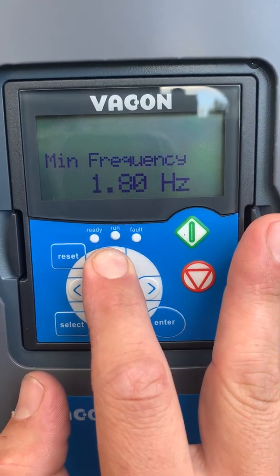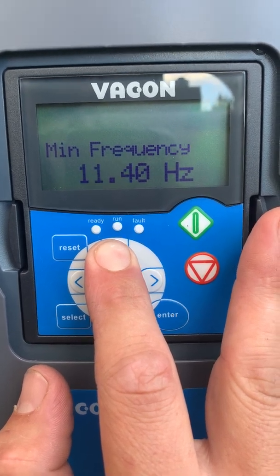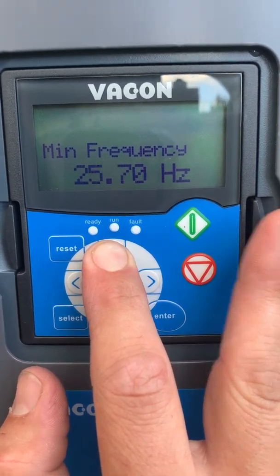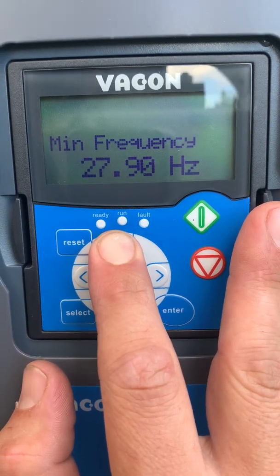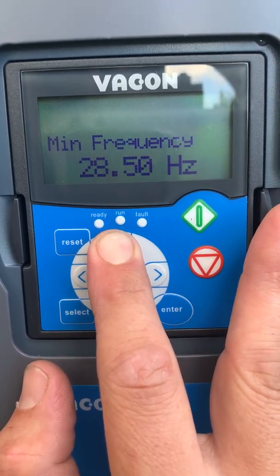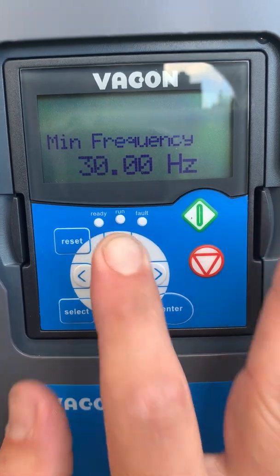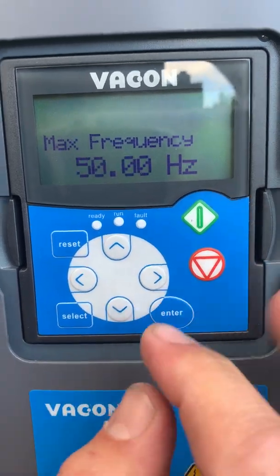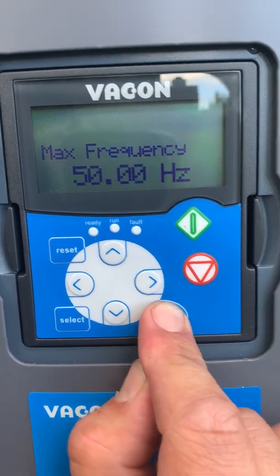Put in our minimum frequency for our compressors. We could set up 25 Hz as standard, but we set up 30 Hz. Maximum frequency: 50 Hz.